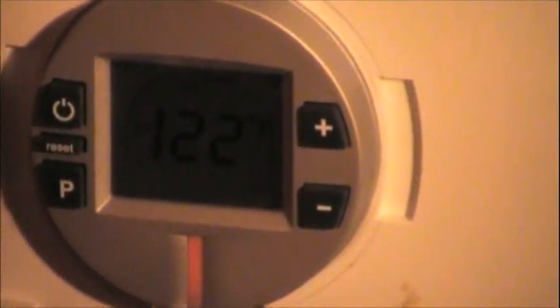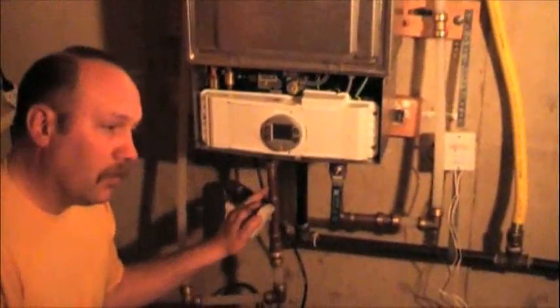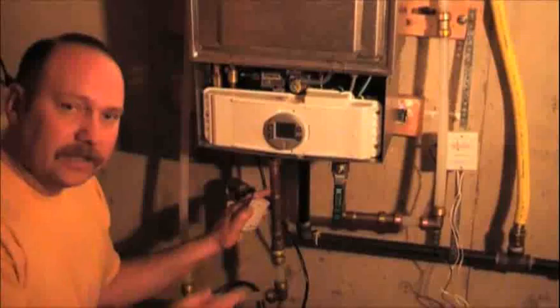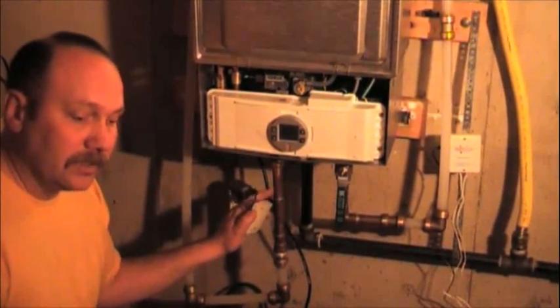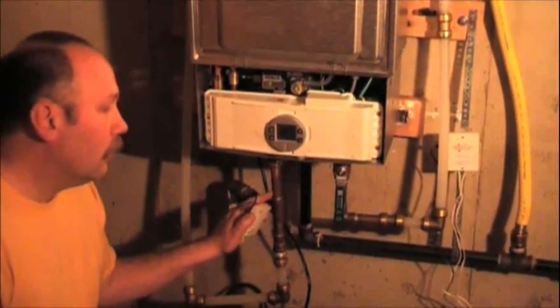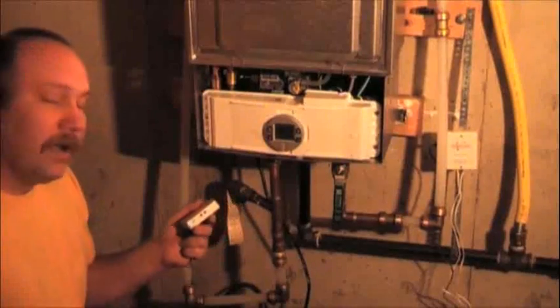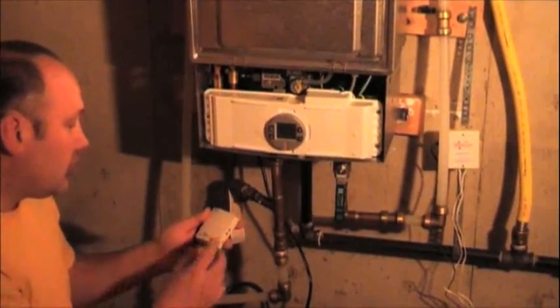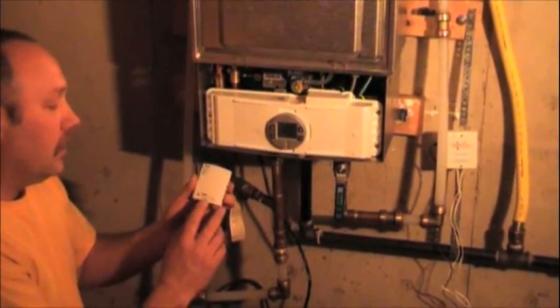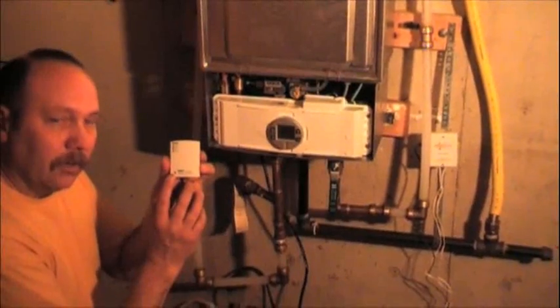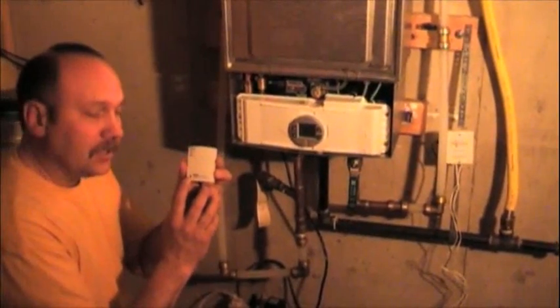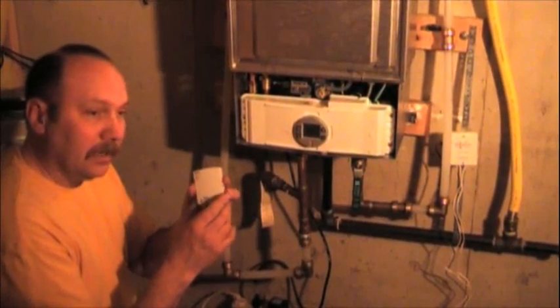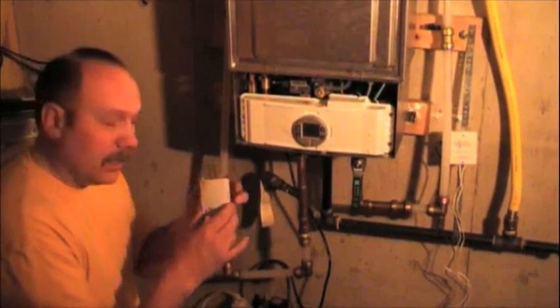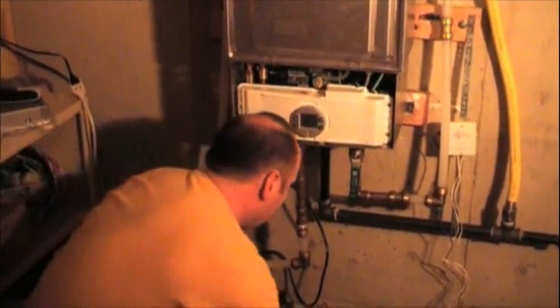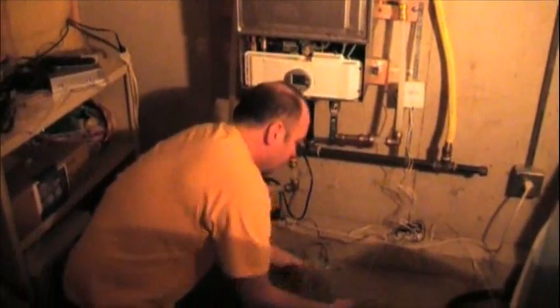So what we're going to do is measure the incoming water temperature and then the outgoing water temperature to see what the delta T is across the exchanger, to make sure that the unit is actually performing up to what we're asking it to. The way that we do that, this HOBO data logger, this is the button that we push right here once we have already attached and plugged in the thermistors. So let me show you how to attach the thermistors.